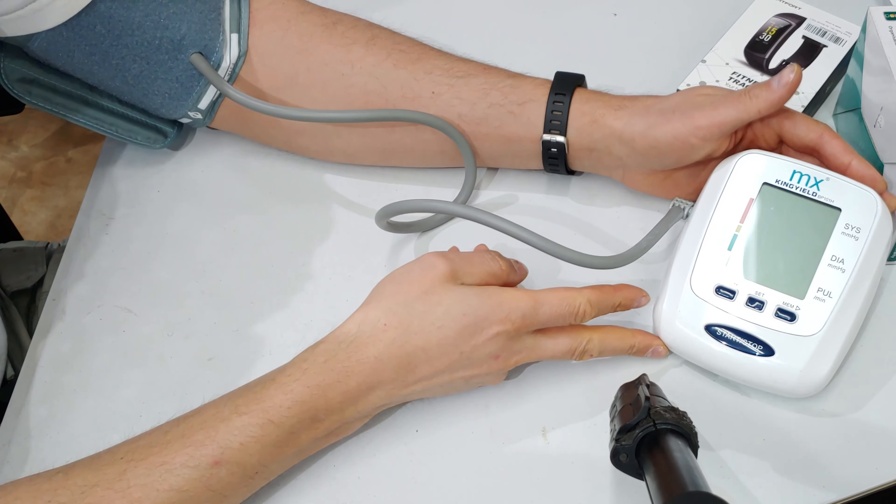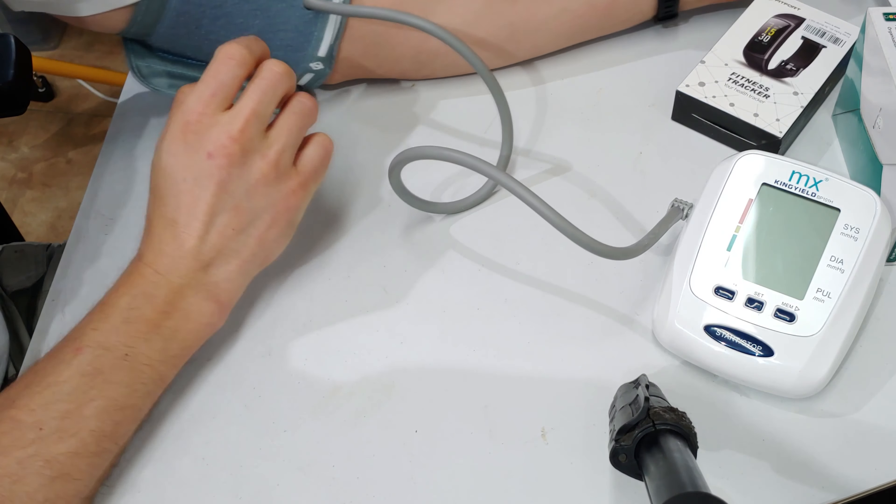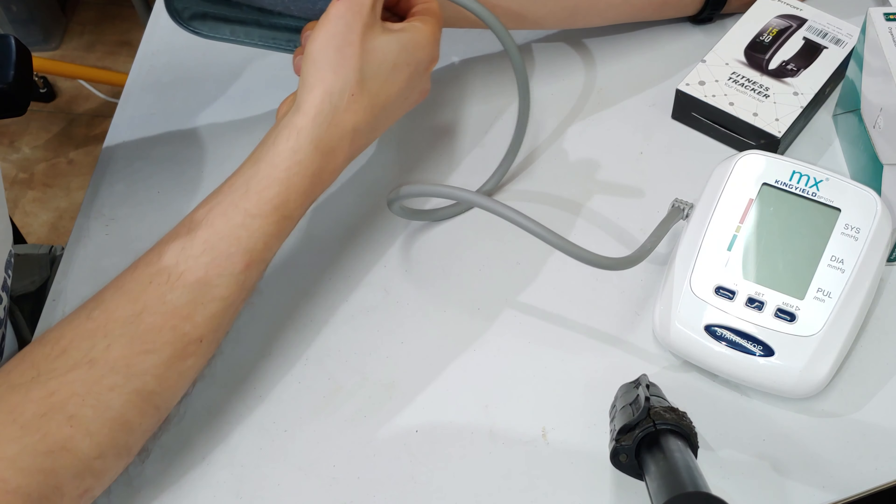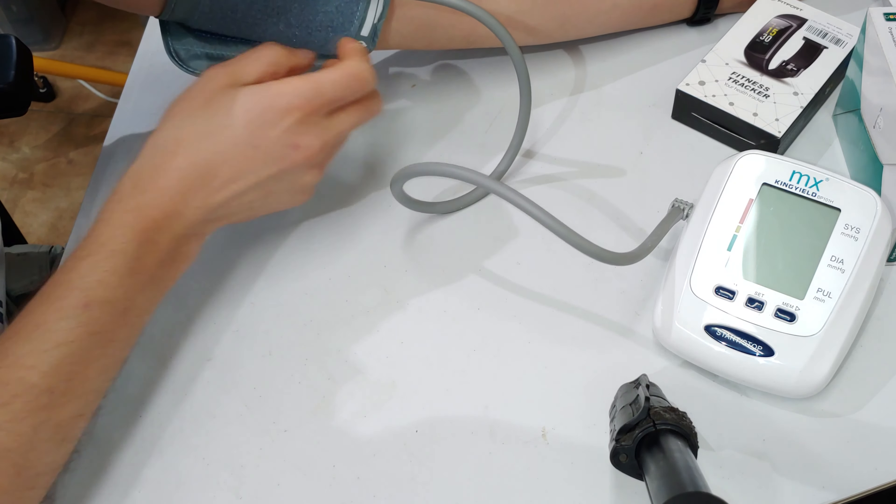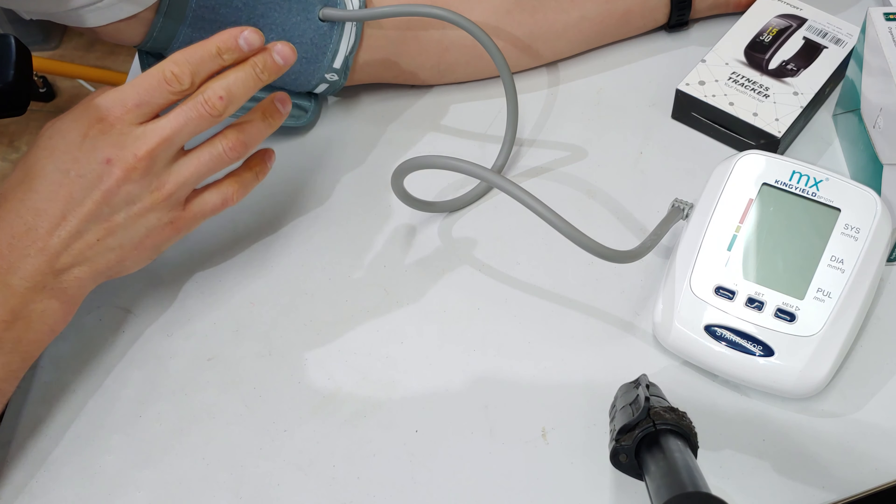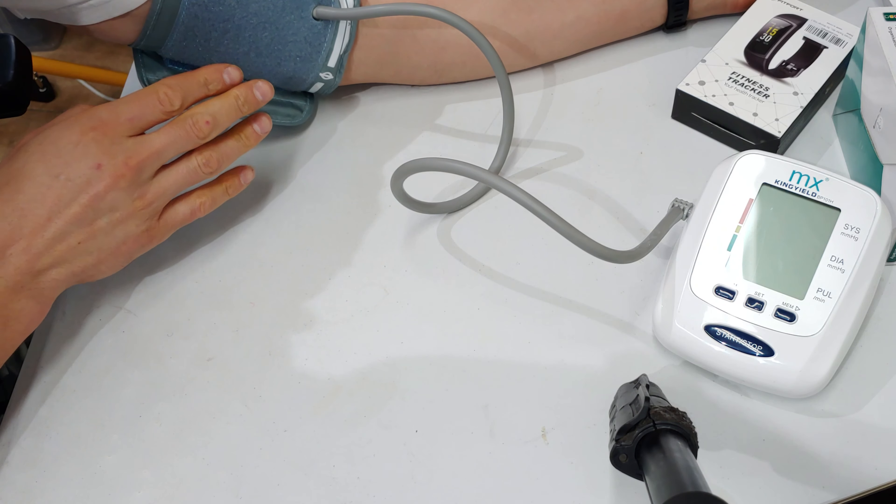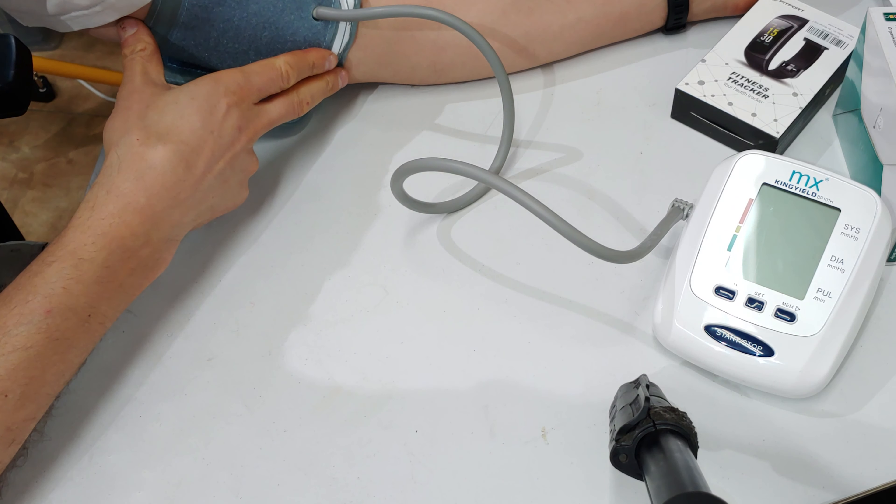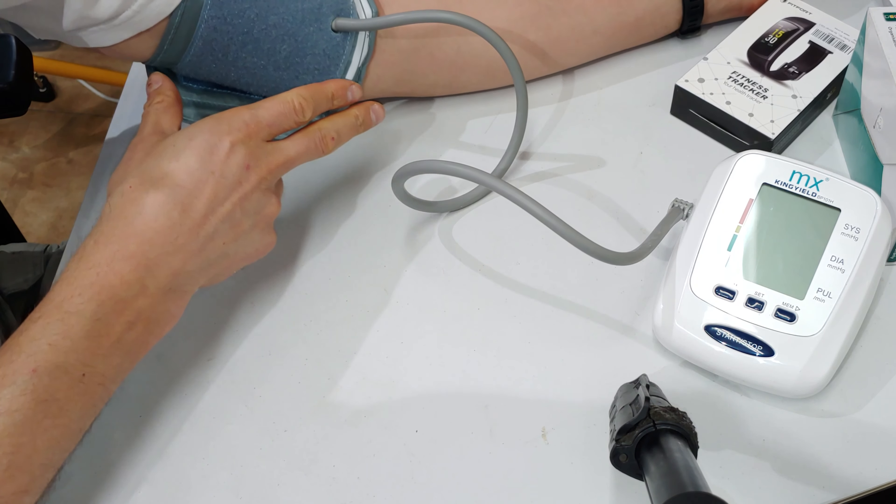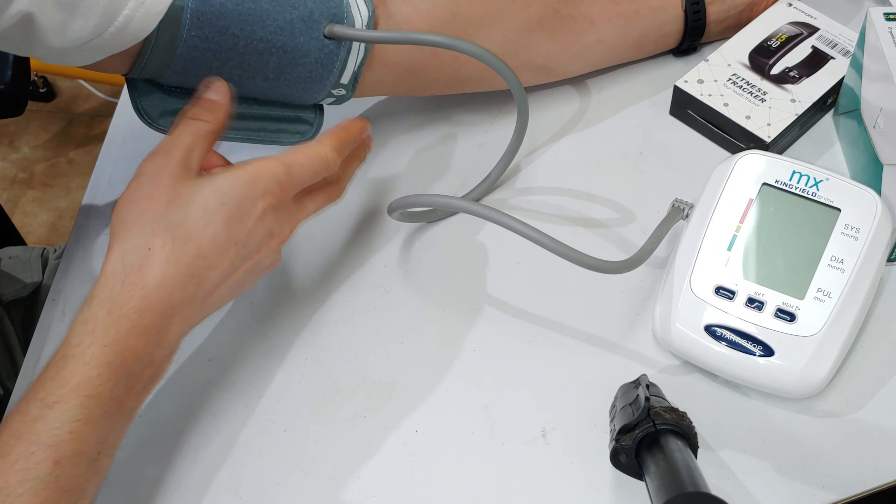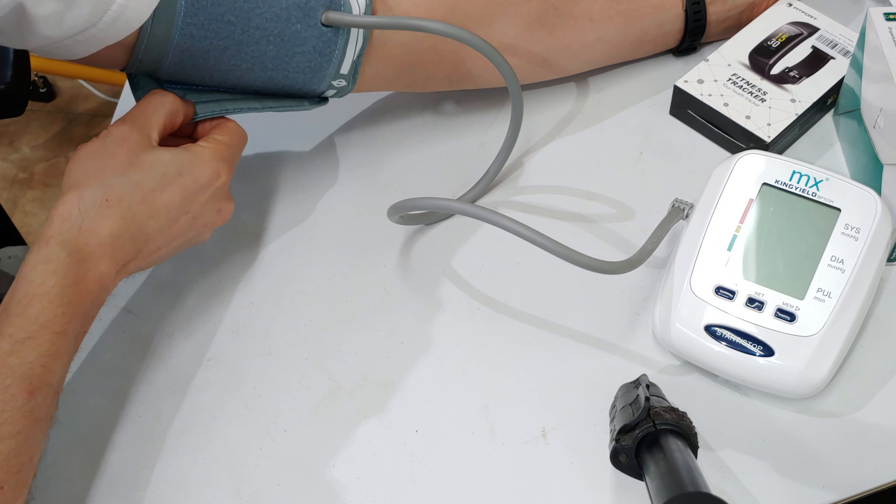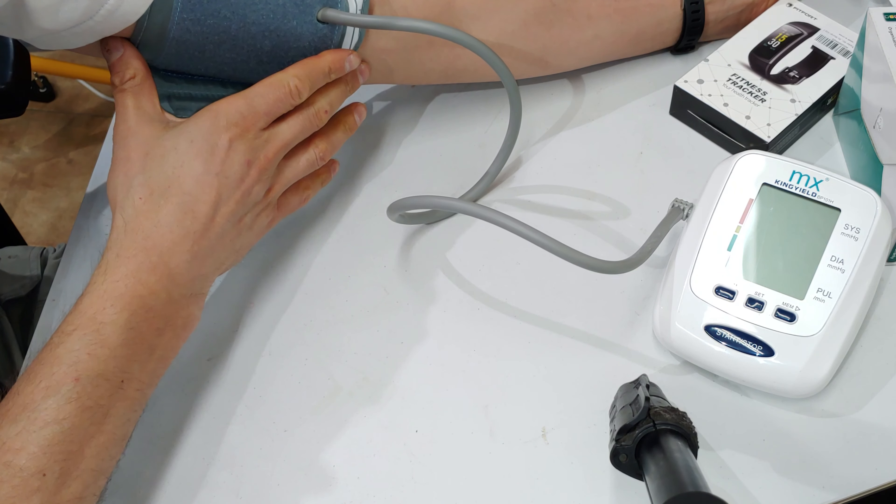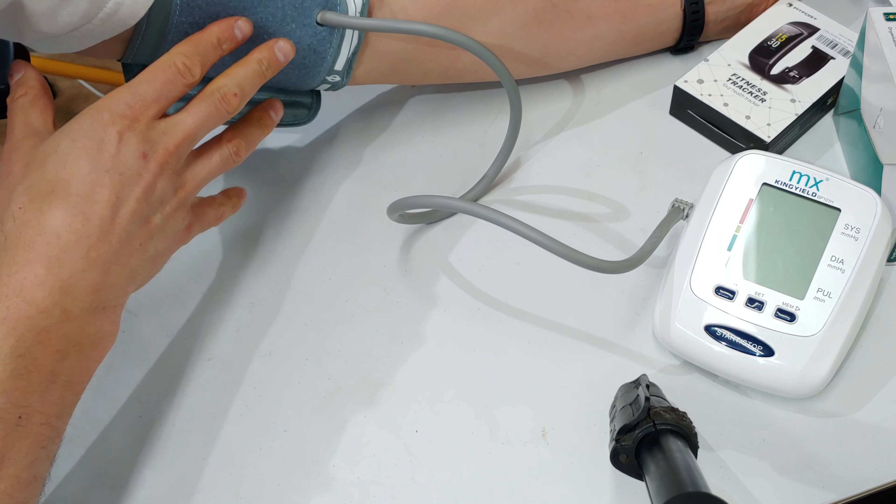I've set it up now, here is the cuff. One of the reasons why blood pressure measurement is often inaccurate is because the cuff size is incorrect. Many times you'll go to the hospital or clinic and they don't have stock of the correct cuff size and end up putting an extra large cuff on a small arm.